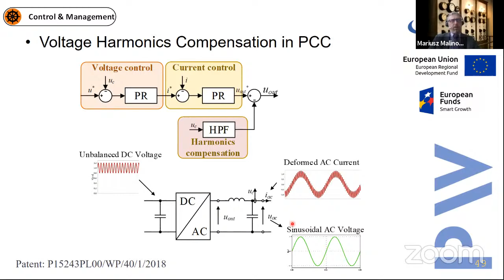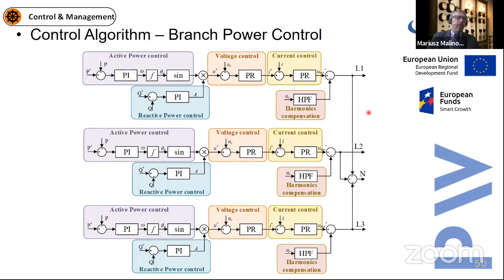distortion. And what was also demanded, as I told, is that each leg of such a 4-leg converter is treated as a single phase converter. Therefore, there is no control in DQ. Rather, the control is in a stationary rotating system based on PR controllers, because in this situation it gives us some freedom to connect any phases to any legs as needed.